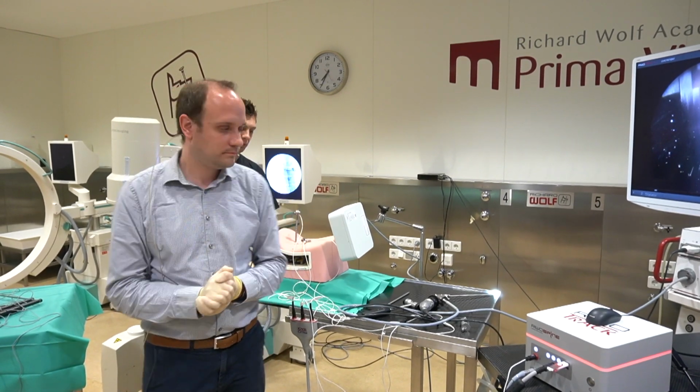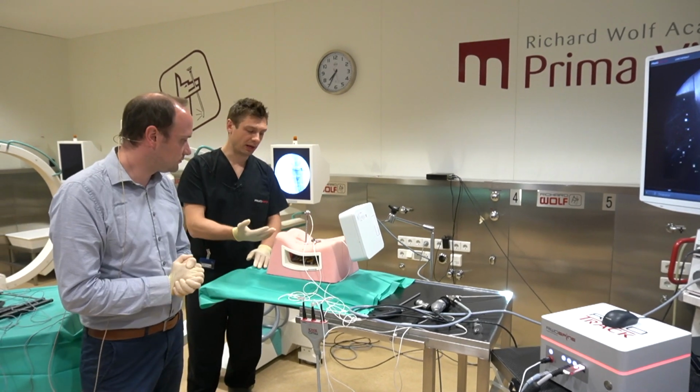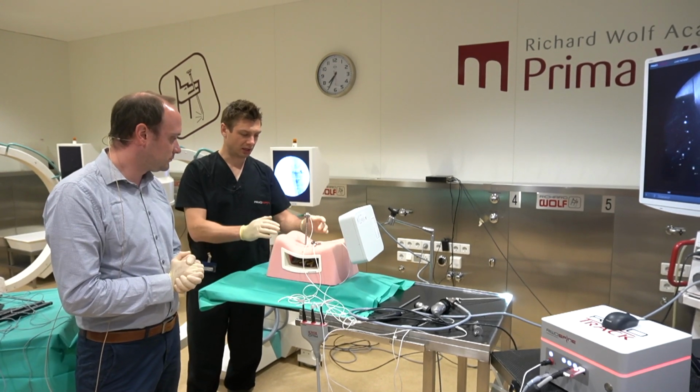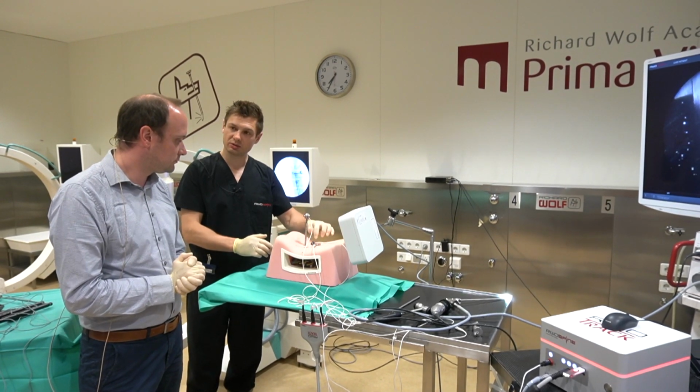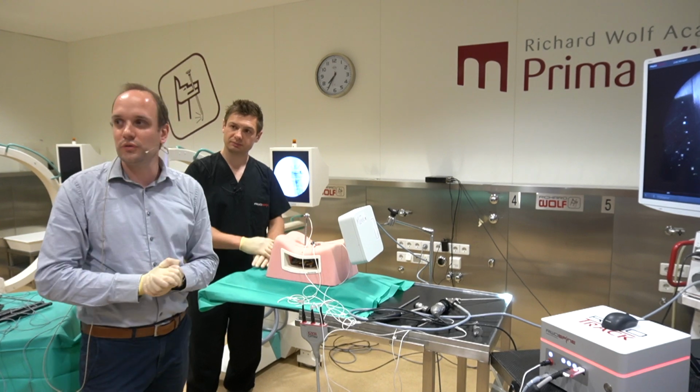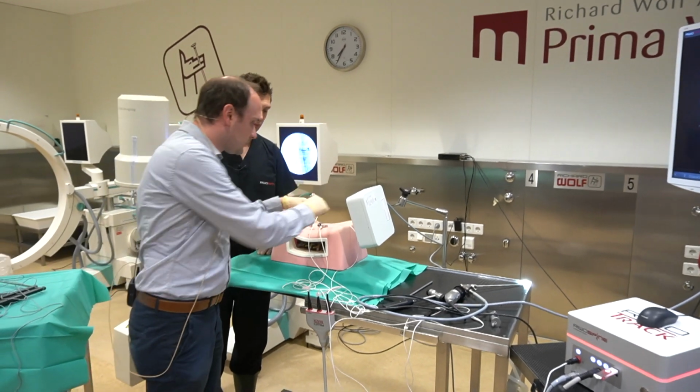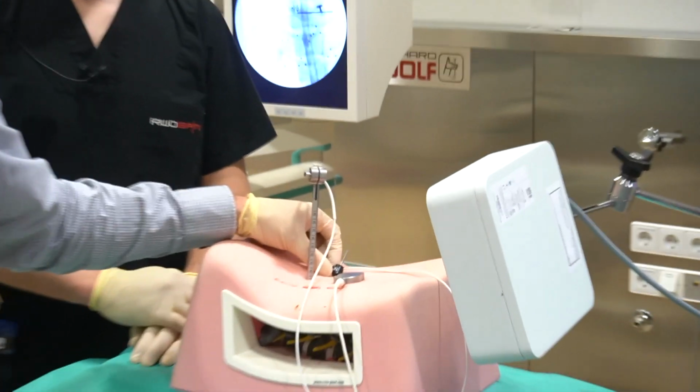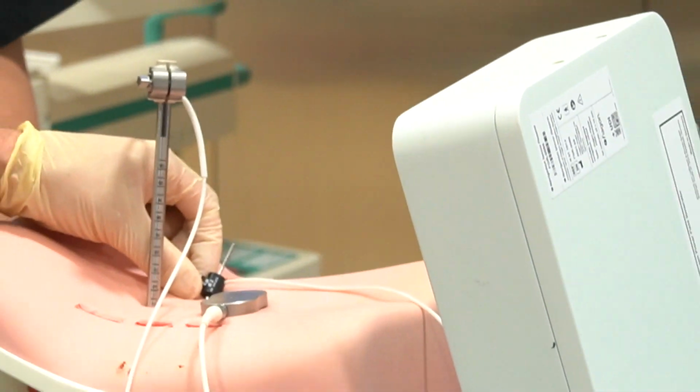And maybe another thing to be more accurate. You have here a second hole. I think that's also for a second K-wire, maybe. Yeah, if you do a lot of drilling, I will quickly remove this. So we're now losing the accuracy of the calibration that we did before.